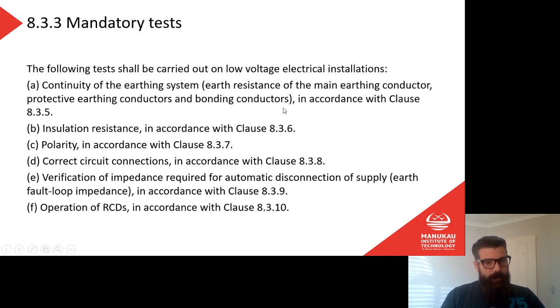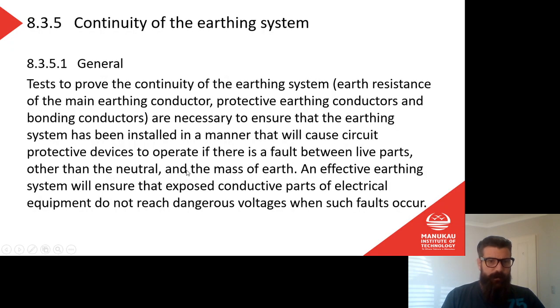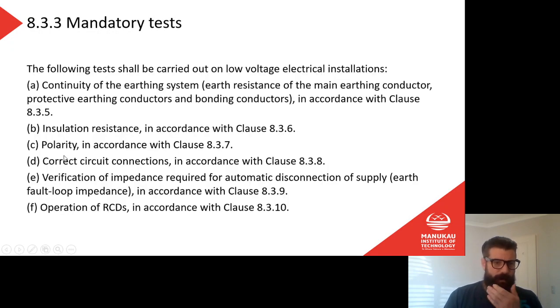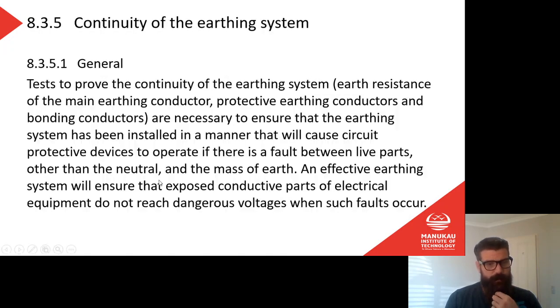Our second mandatory test is insulation resistance. Third is polarity. Fourth is correct circuit connections. Fifth is verification of impedance required for automatic disconnection of supply, which we call earth loop impedance, or earth fault loop impedance, and operation of RCDs. So a little bit more detail on each of those.